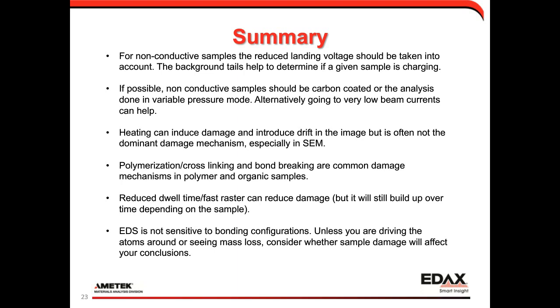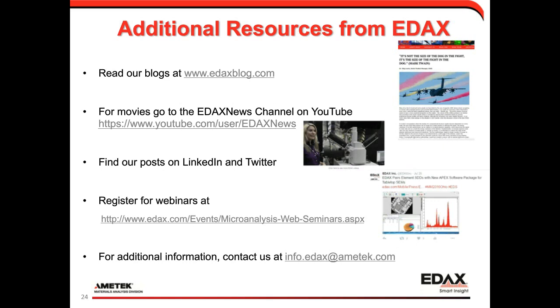Very high beam currents — in the 50+ nanoamp range — are where mass loss becomes significant within a reasonable time, which is mostly relevant for WDS/microprobe work. In TEMs, current density is much higher, so mass loss can occur quite rapidly. For more details on damage mechanisms in both SEM and TEM, I recommend the Egerton paper referenced at the bottom of the slide. That concludes the main presentation.